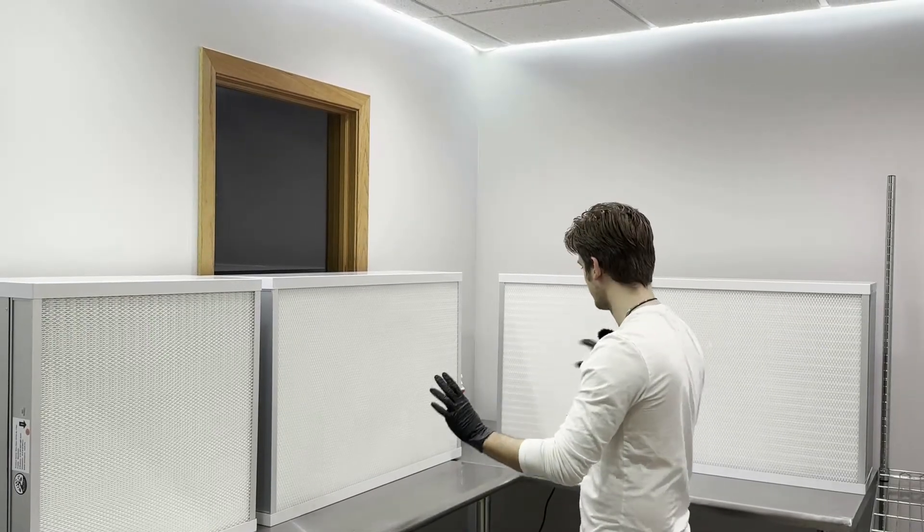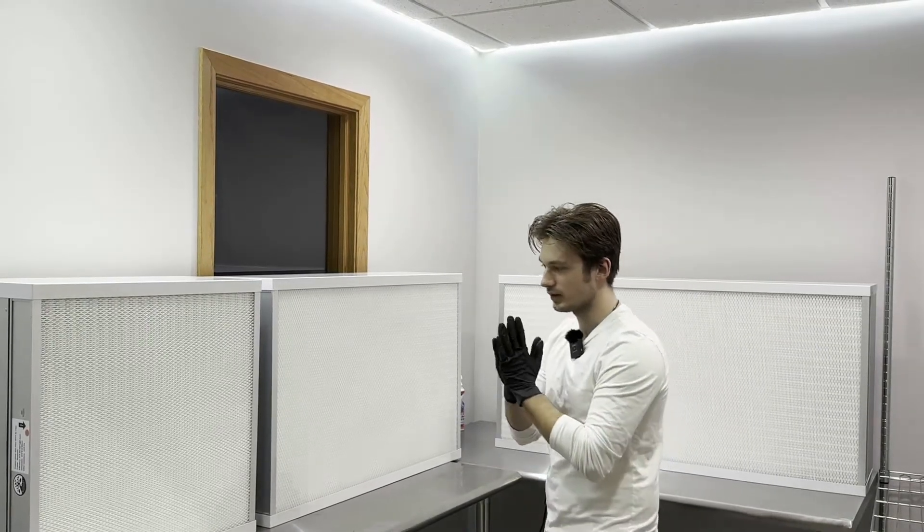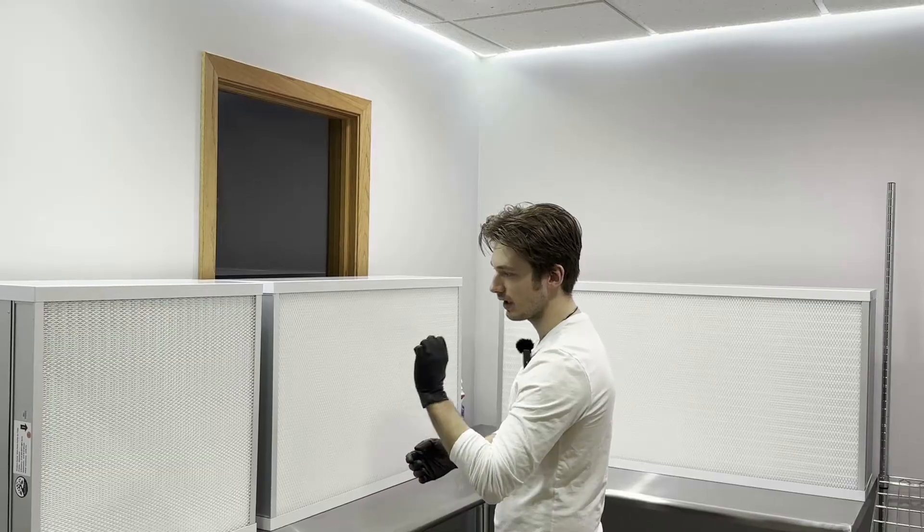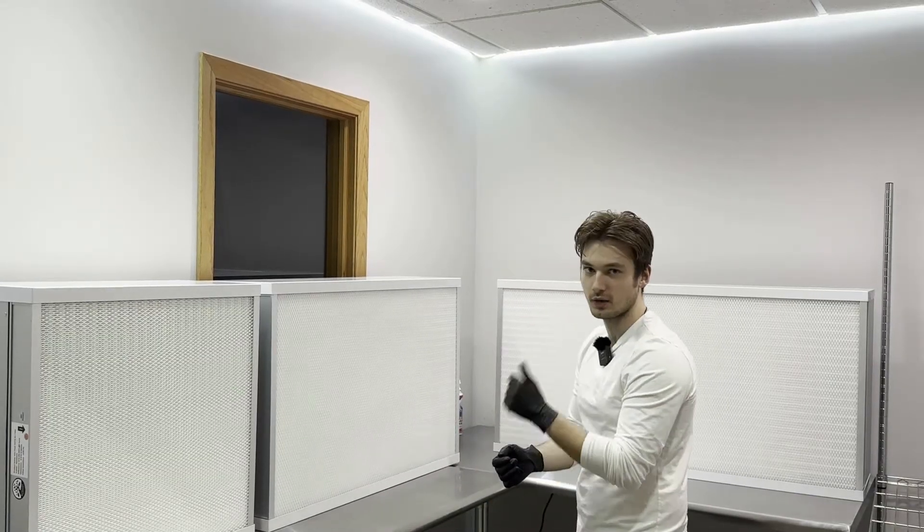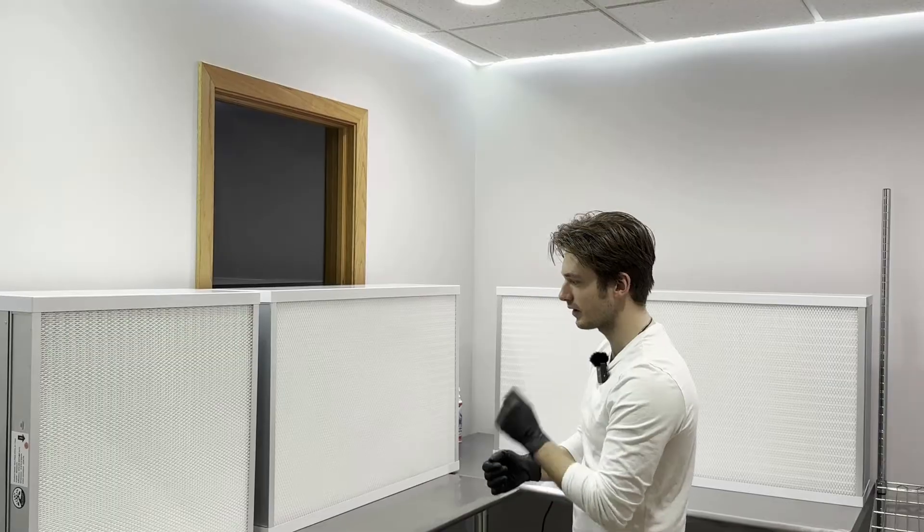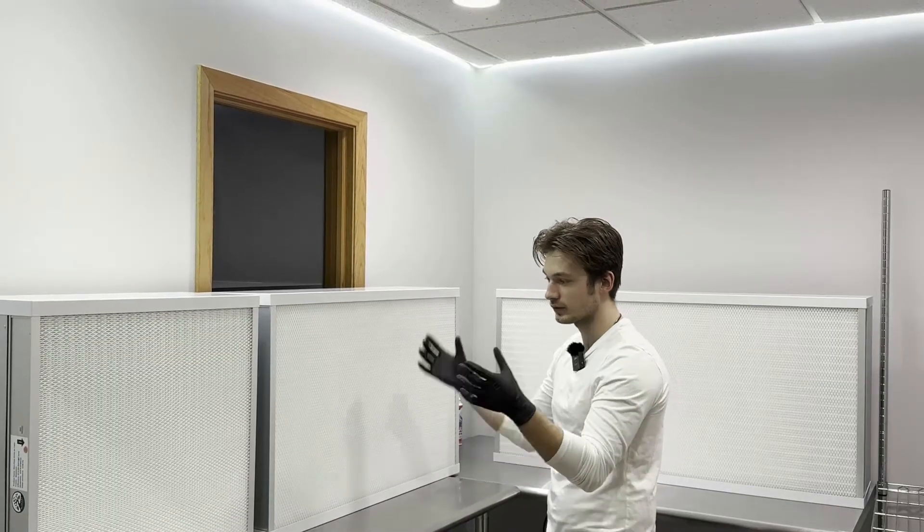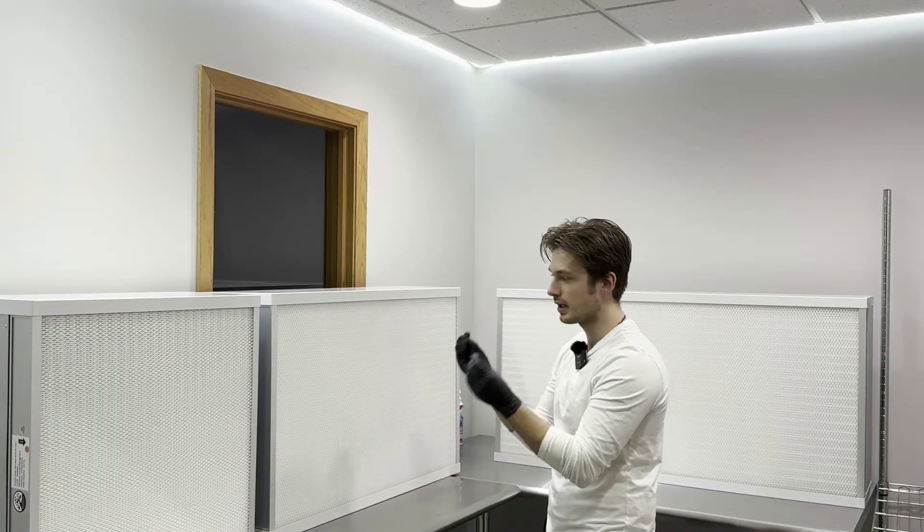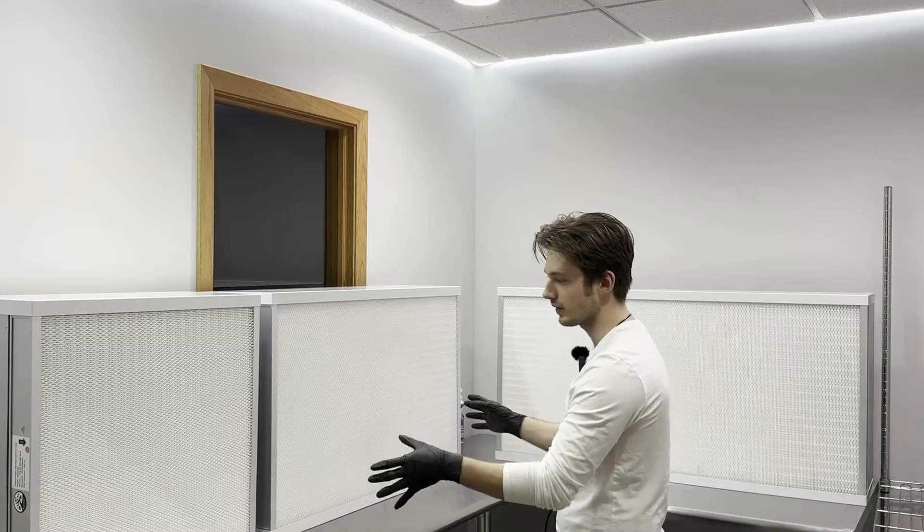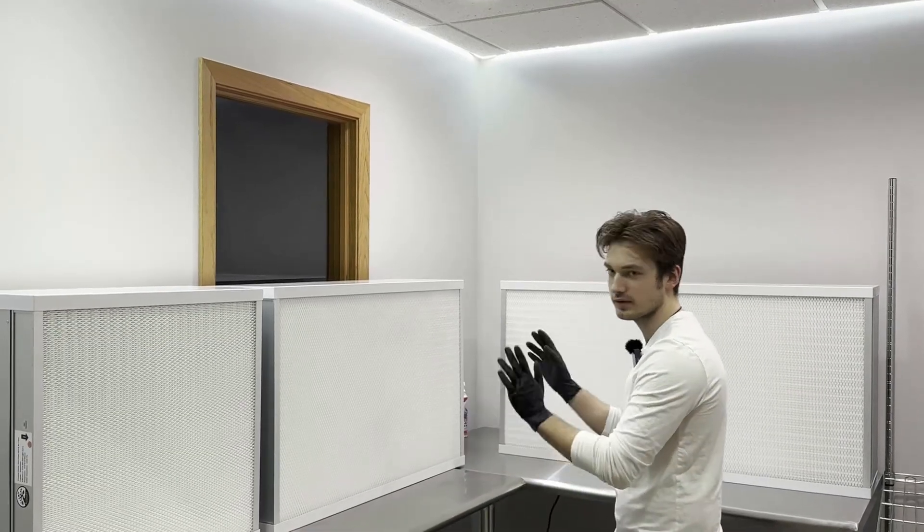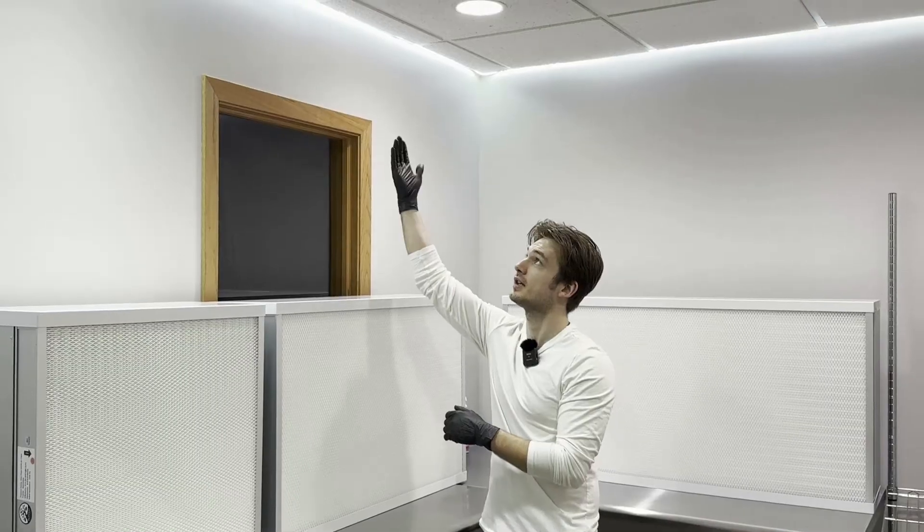All three fan filter units have the same H14 rated filter, which filters out 99.99% of contaminants in the air down to 0.3 microns. This means you can use these units traditionally like a flow hood, or install them into your ceiling space to create a true clean room.